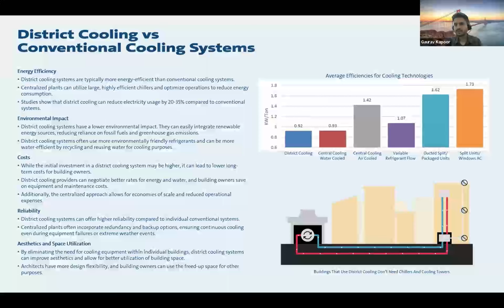Now, district cooling versus conventional cooling systems has already been discussed. DCS is way more sustainable and consumes very little kilowatt per ton compared to other cooling technologies. As we can see on the top right of the curve, district cooling on average, this is an old sheet, but currently it consumes 0.75 to 0.8 kilowatt per ton, whereas split units, which are the majority share in India right now, consume 1.73 kilowatt per ton. And the other major benefit, besides all the factors already conveyed by sir, is the aesthetics, which has also been touched upon, that you remove all these machineries from a connected building.